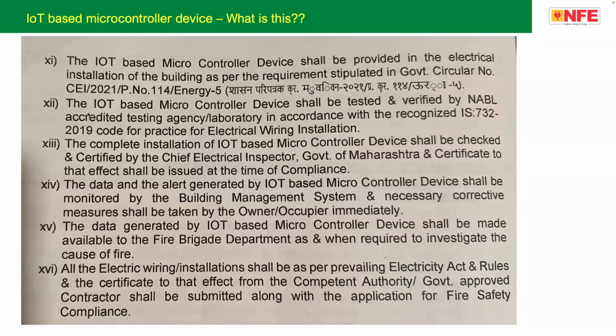Number two, the IoT-based microcontroller device shall be tested and verified by a NABL accredited testing agency laboratory, in accordance with the recognized IS 732-2019. As I said, IS 732 is not a product standard, it's an installation standard. Nobody can test one product as per IS 732. If somebody claims this, you can be 100% sure that it's a fraudulent claim.